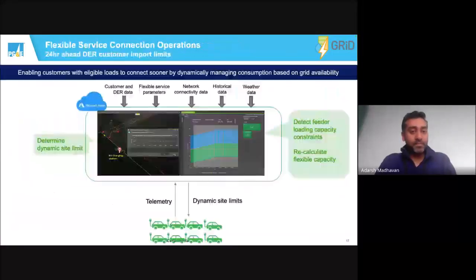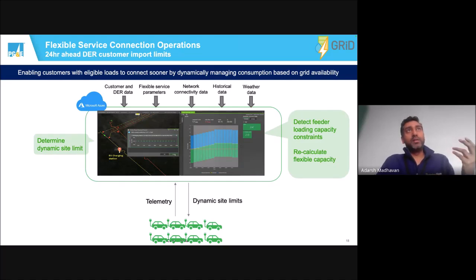How we do this is, again, using our DERMS platform. But what does DERMS actually do? DERMS monitors the AMI loading of all the other customers connected to the feeder. It monitors the loading of the bank or the constraint device, and it comes up with a forecast of how much available capacity there will be on the grid, then allocates that capacity to the flexible service connection site that is connecting to that feeder.